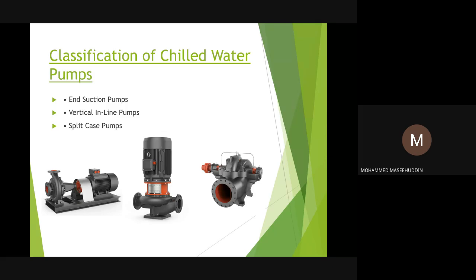These types of pumps are easy to remove, and are also called BPO type pumps, which is back pull out type, because without disturbing the piping connections, we can easily maintain these pumps. We can take out the pump itself, open the pump and replace the bearings, the mechanical seal, shafts, etc. We can do it without removing the actual piping connections. So that is the reason why it is called a back pull out type of pump. And this is mostly used in the primary circuit of the chill water system.